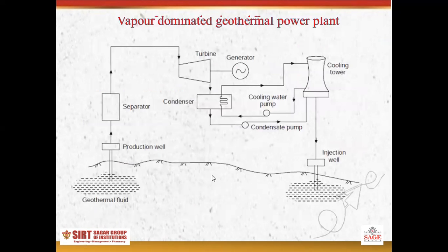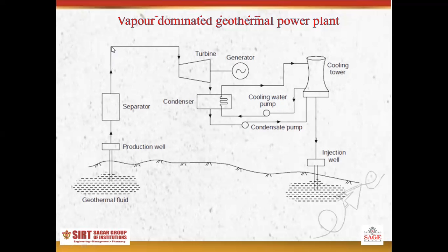Here you can see the schematic diagram of a vapor dominated geothermal power plant. The dry steam tapped from the well is collected and filtered in the centrifugal separator to remove the abrasive particles. This steam is then passed through the pipes to run the turbine.